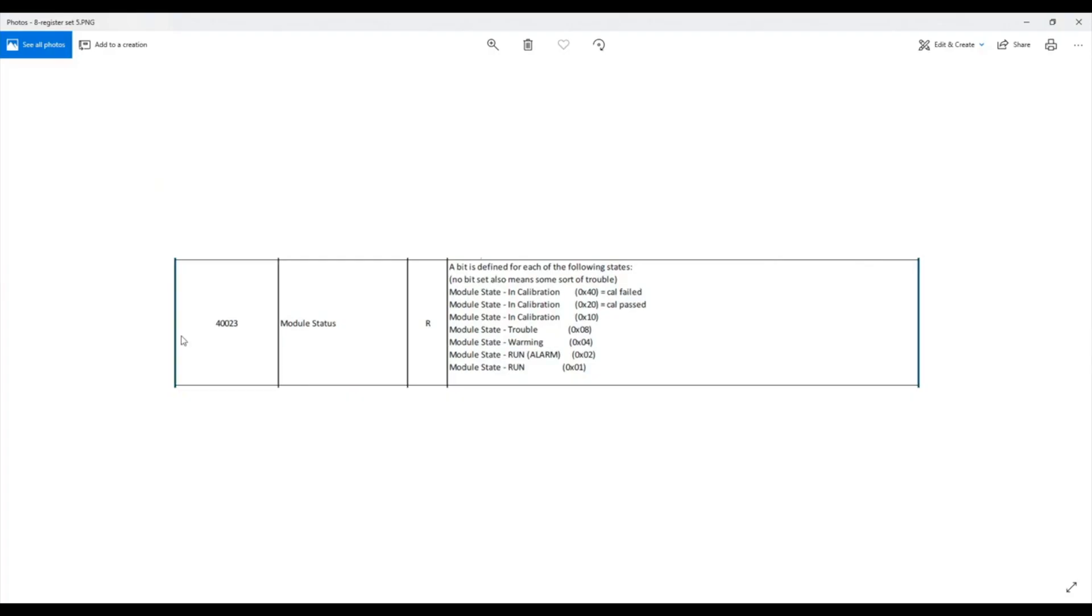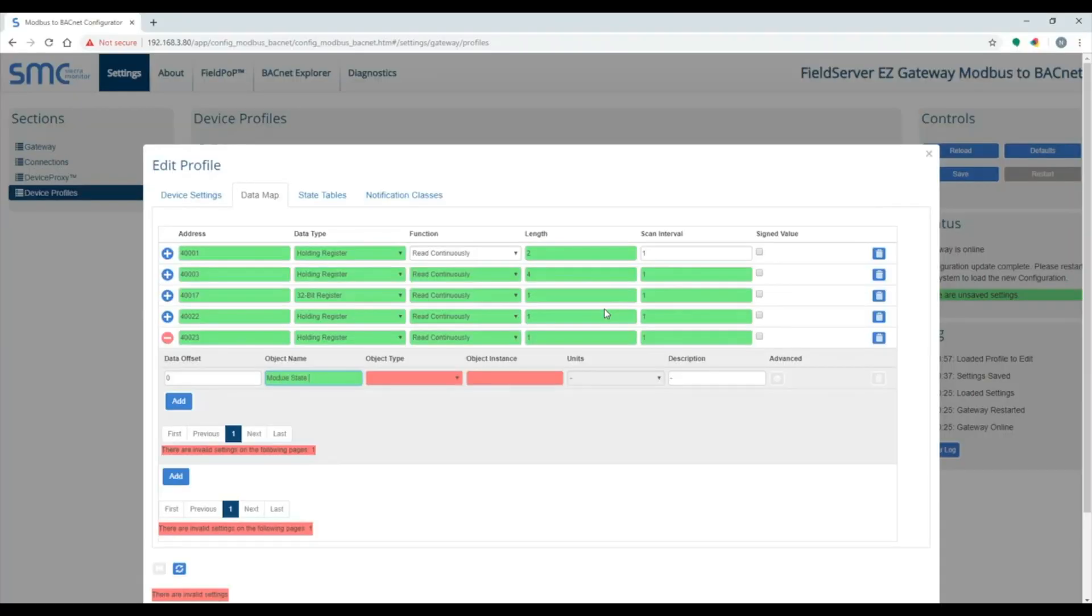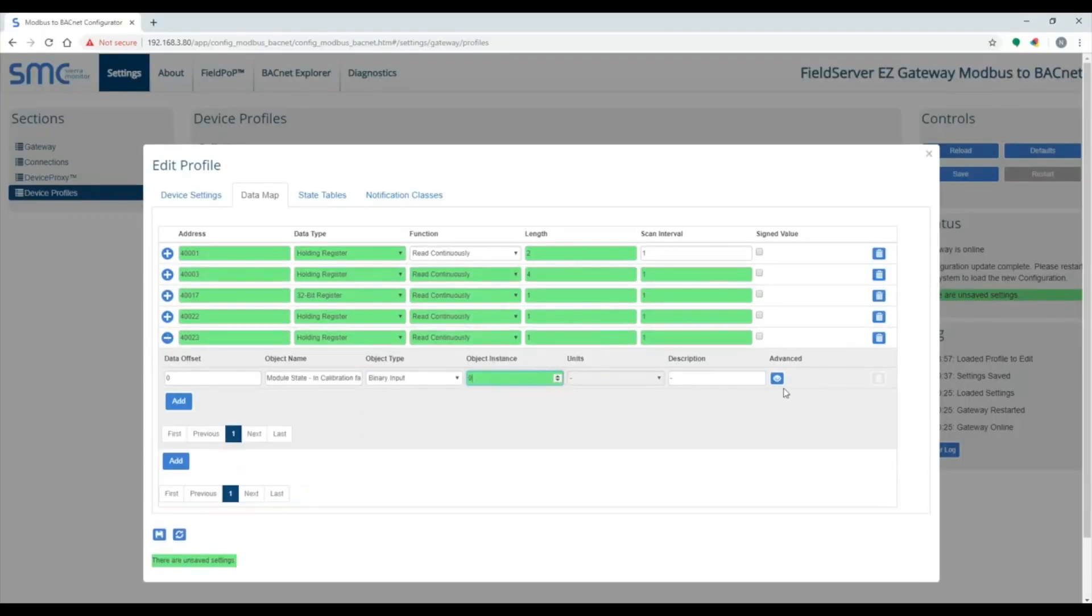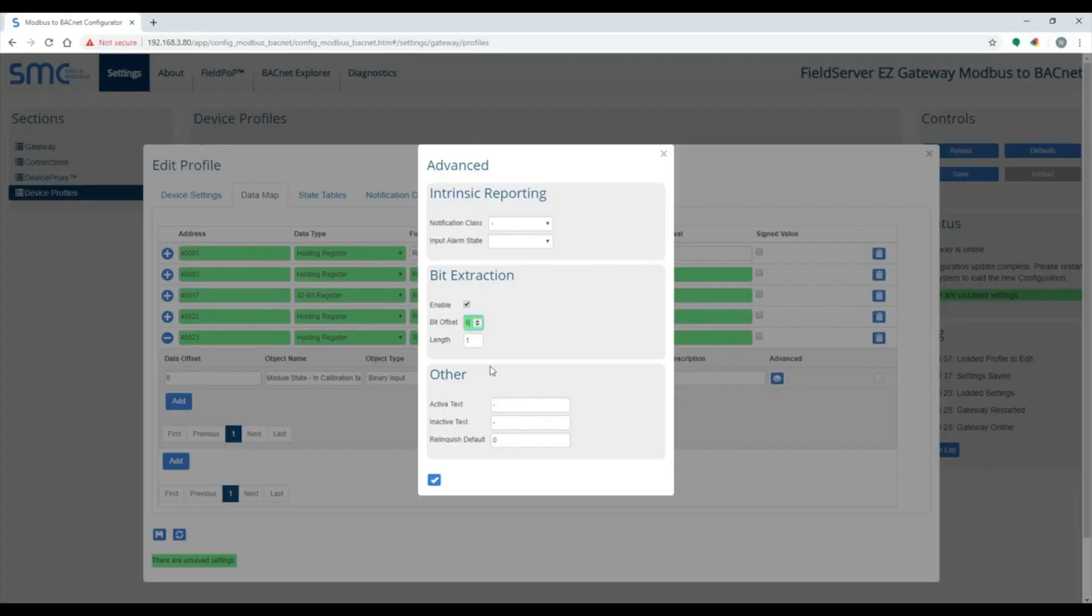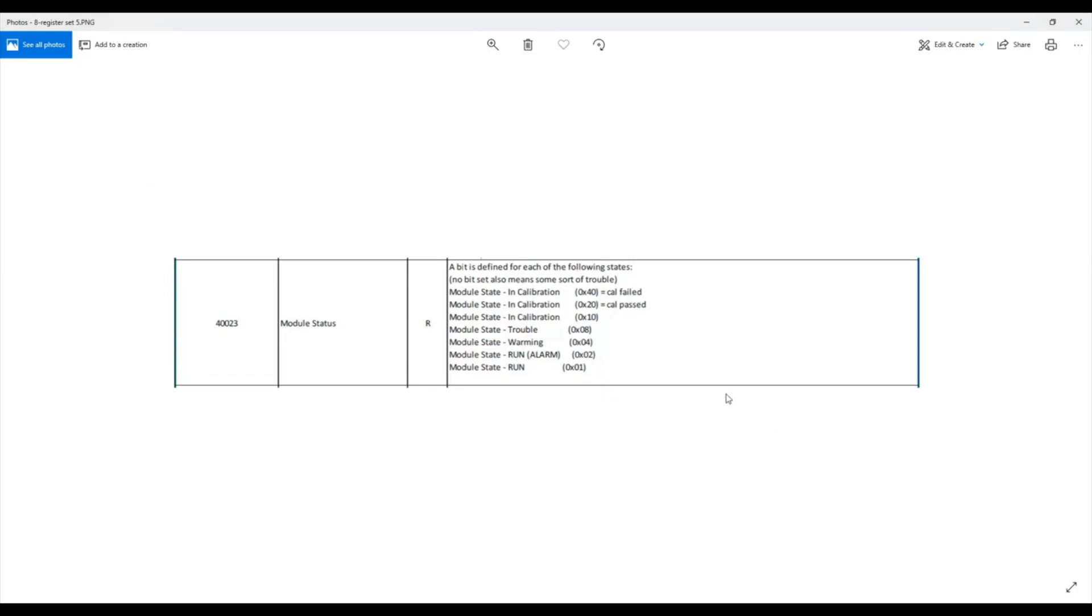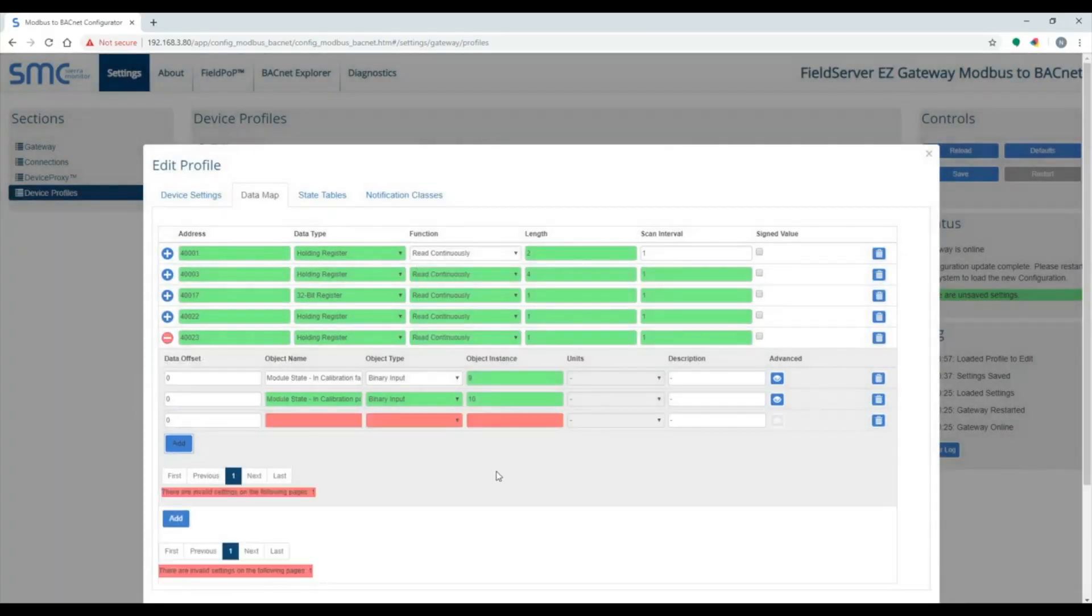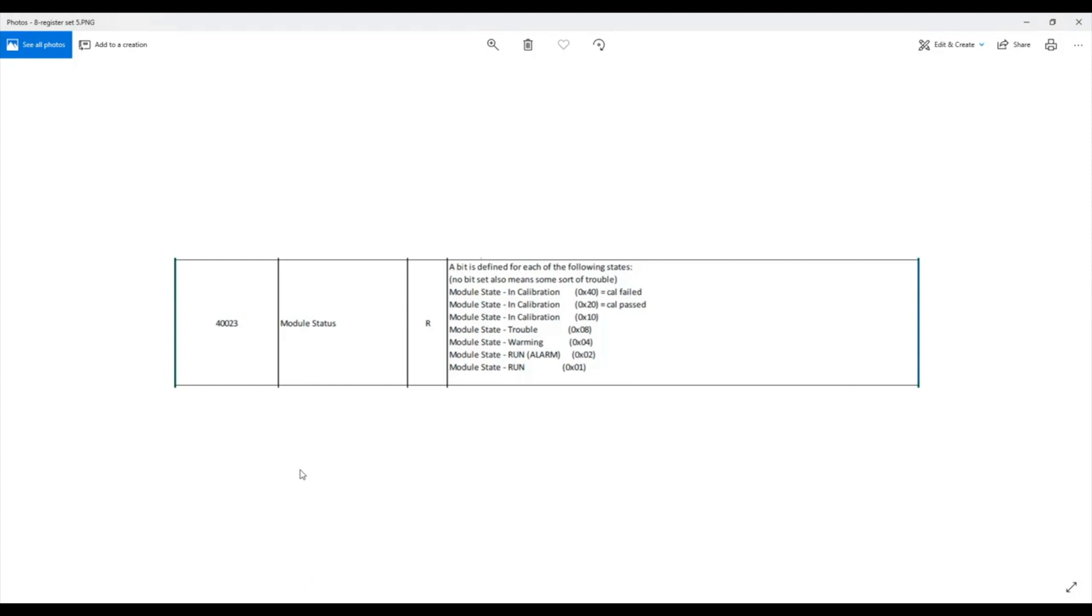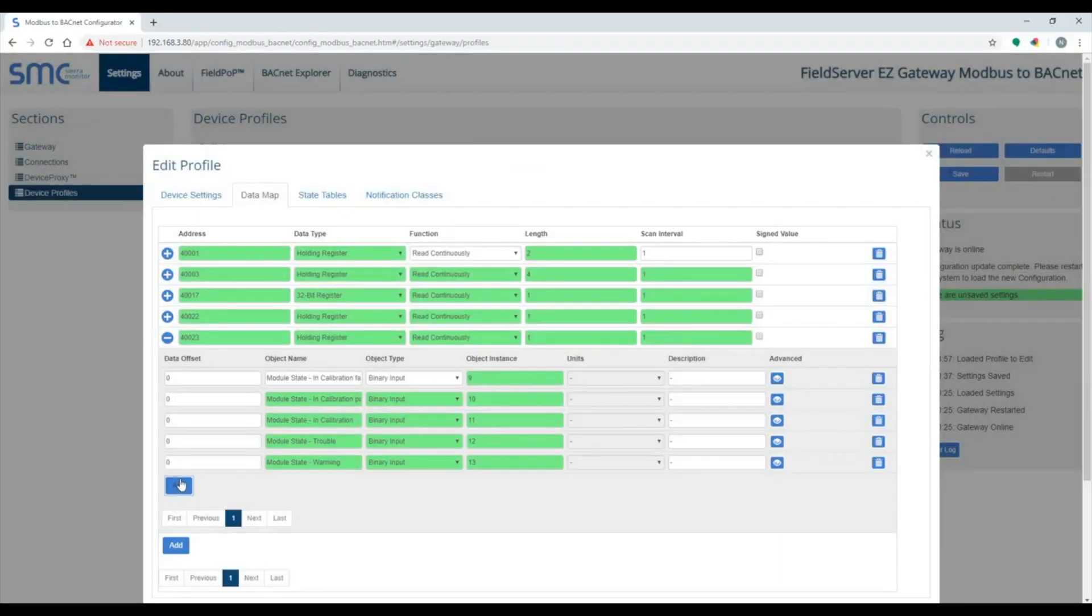The last point is a bitmap. There are multiple bits mapped in this 16-bit integer. To map the bit to a BACnet object, go to the advanced section and click on enable under bit extraction. Then specify the bit offset. Module state in calibration failed is 0x40, which converts to binary bit number 6. Module state in calibration passed is 0x20, which converts to binary bit number 5. Module state in calibration is bit 4. Trouble is bit 3. Warning is bit 2. Run alarm is bit 1. And run is bit 0.